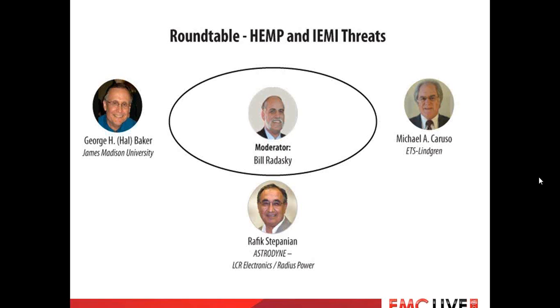One comment I'd like to make is there's a misunderstanding with a lot of people about what lightning protection means. Almost never is lightning protection adequate for a direct strike to your facility. The lightning protection that works is for lightning that is a bit further away. The idea that people are building lightning protection to handle 200,000 amperes hitting their house or building is not the case—there will be some damage. So not even the lightning protectors can handle that.